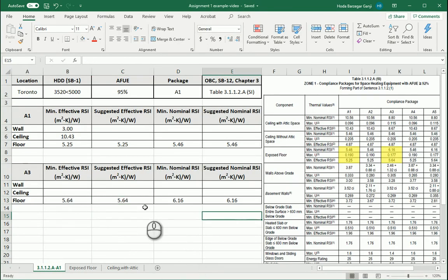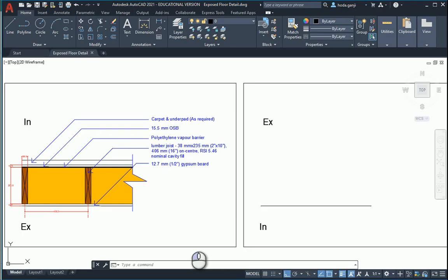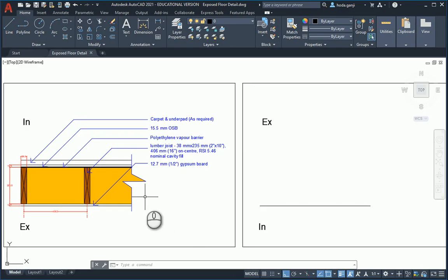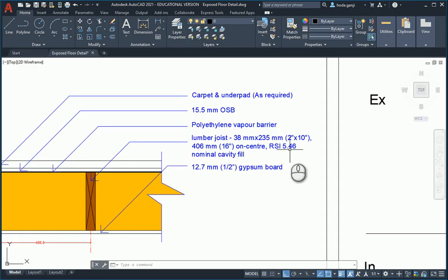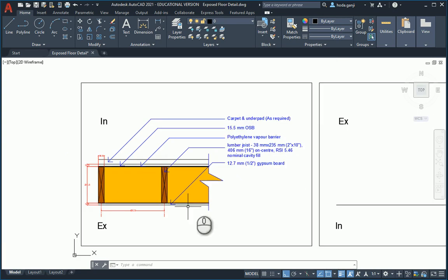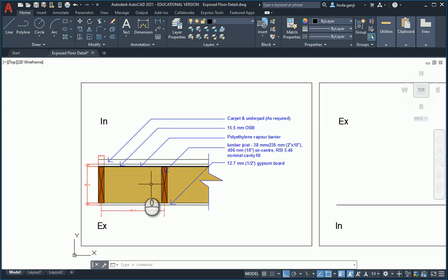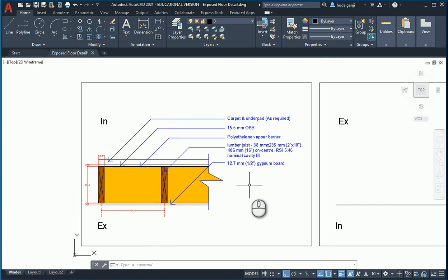When you draw the detail it is basically exactly the same, except that in the note you need to say the RSI is 6.16. The dimensions are the same because the joists are the same. The layers and everything is the same — it's just a different insulation with a different nominal value.